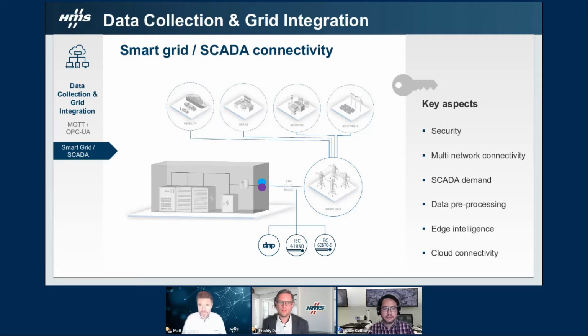On a higher level, for external communication from the BMS or EMS, battery energy storage systems typically use Modbus-based communication. CAN is mainly used inside and with the battery modules. Power grid SCADA typically uses energy protocols like DNP, IEC 61850, or IEC 60870. Heavy industries typically use industrial protocols like Profinet, Profibus, or EtherNet/IP. Renewable and mobility typically use industrial protocols, Modbus, and/or Open Charge Point Protocol.